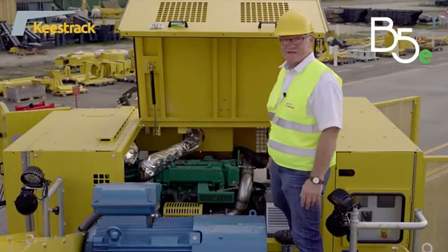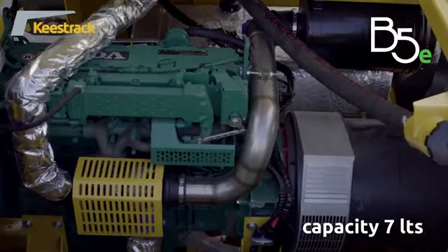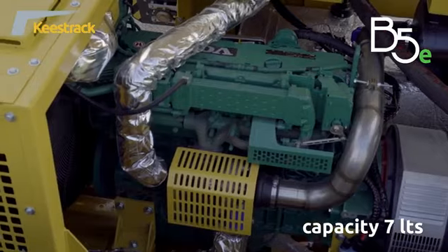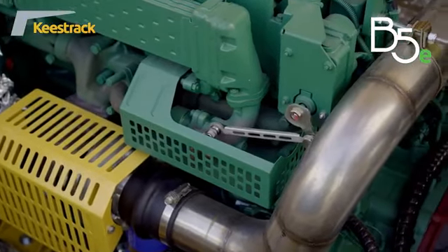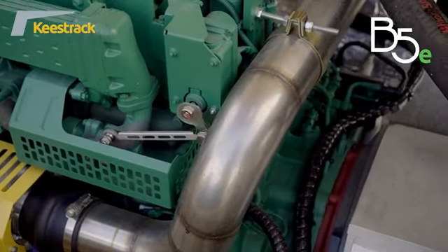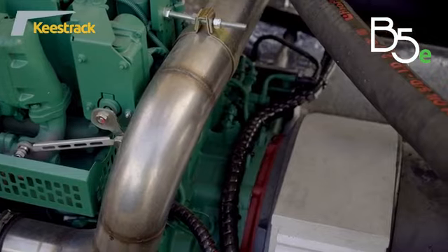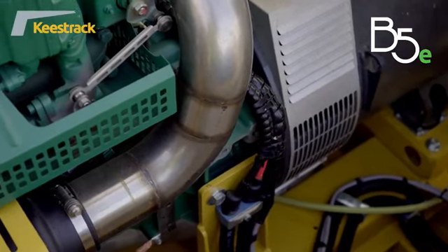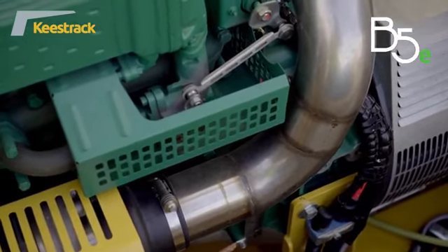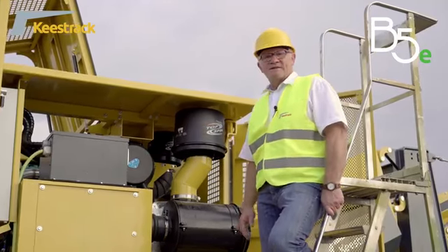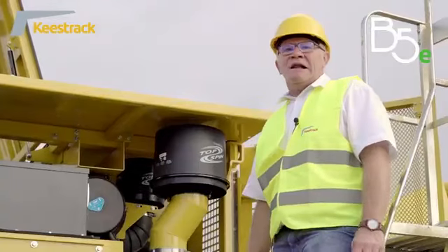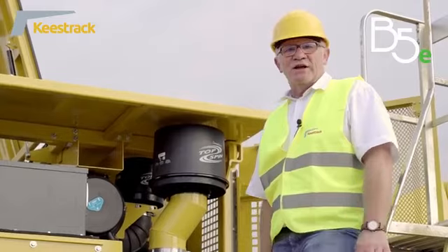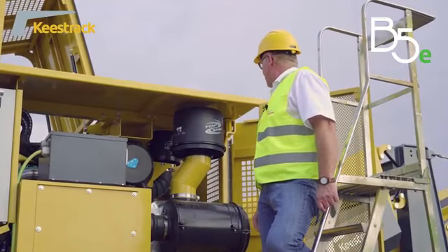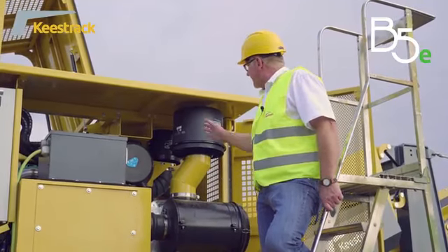So the drive of the whole machine is done by this engine unit. It consists of a Volvo engine with 251 kilowatt and an alternator with 320 kVA. The engine unit is in a compartment for noise absorbing, and even the diesel fuel tank is inside the unit. So this Volvo engine has an EU Stage 3A. It's a fixed speed engine and it is running at 1500 RPM. Low speed for low noise emission and low CO2 emission. In the next step, a Cummins engine for Stage 5 is also available.